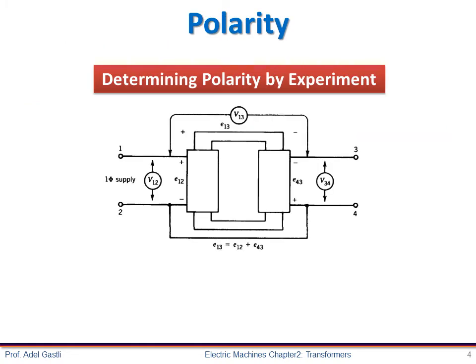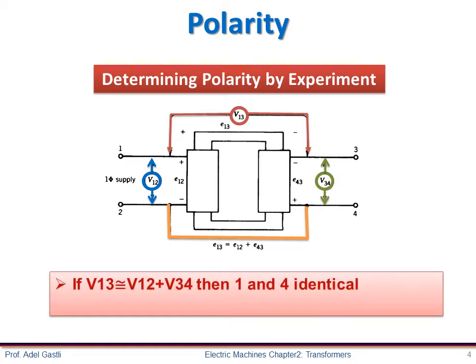Polarity can be determined by experiments, as shown in this figure. We connect three voltmeters as shown: one measuring the input voltage between terminals 1 and 2, the second between terminals 1 and 3, and the third between terminals 3 and 4. Terminals 2 and 4 are electrically connected with a conducting wire. Then, if V13 is nearly equal to V12 plus V34, we can say that terminals 1 and 4 have identical polarity.